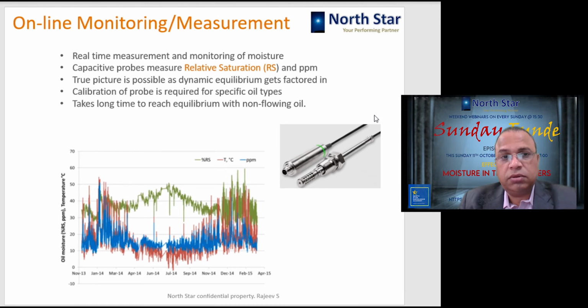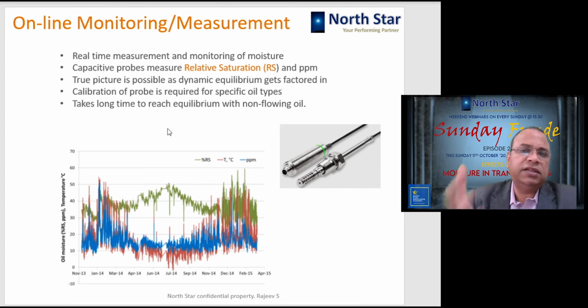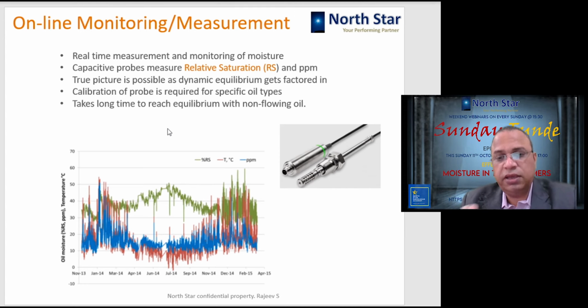Okay, so capacitive probes, Vaisala is the number one company making these probes. These probes are quite sensitive and quite good, but they also have their own limitations, because if strong acids are present, then the capacitance of the probe gets affected. If the oil type is different, then some calibration is also required. But other than these two limitations, they give you very accurate results.